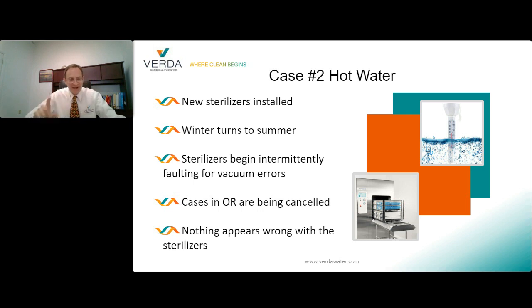However, the second year they were operating with these new sterilizers, they started seeing their sterilizers having faults, or vacuum faults to be precise. So like the horror story of case study one, the faults became more frequent, resulting in rework and re-sterilization of instruments that had been interrupted in the sterilization cycle. That rework started impacting the surgical team's ability to perform the surgeries. And I'm sounding like a broken record, right? Then they started having to cancel surgeries. So what's going on here? I mean, aren't they doing everything correctly when it comes to water quality? So the issue is small, but it's a significant one.